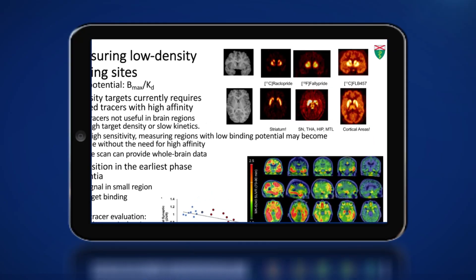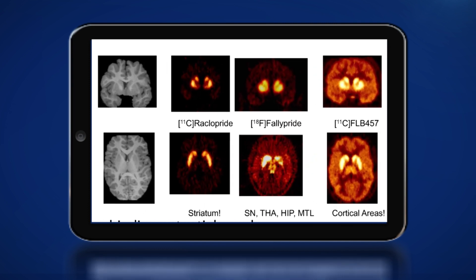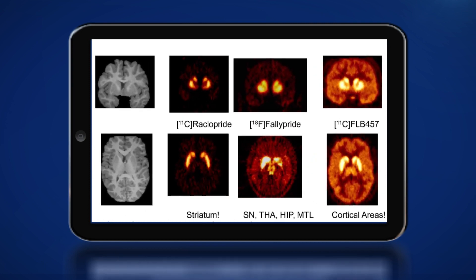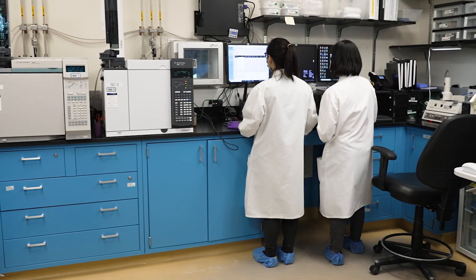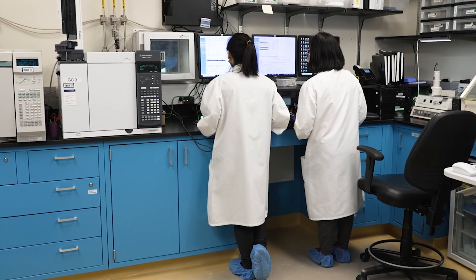It is also long for the brain — 50 centimeters — enough to count the vast majority of the events coming out of the brain, but also with much higher resolution. We're going to have resolution under two millimeters, and that's going to really let us focus on these very small structures with very high sensitivity. Not only is the resolution great, but the statistics are great. We can measure small changes in subjects from one day to the next.